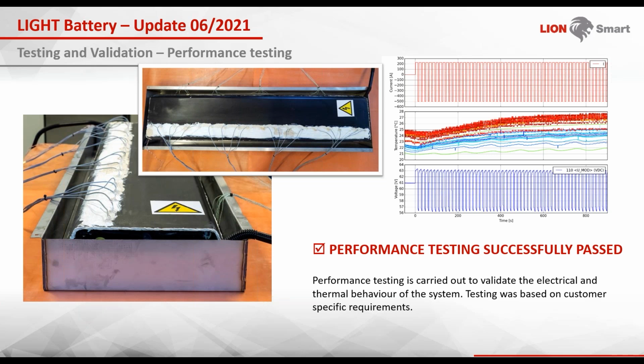You can see an example setup on the left here. Basically, we set up these modules with many sensors. As we have our own BMS built inside the battery, we need to check that the voltage measurements of the BMS are correct, so this is tested by voltage sensors. We are also checking that the temperature measurement and distribution, and the cooling, are working correctly. For that, we bring a lot of temperature sensors into these modules, and this way we can validate that our battery is doing what it should do.